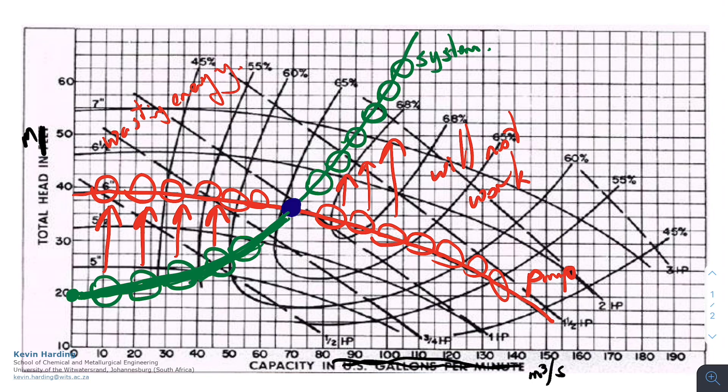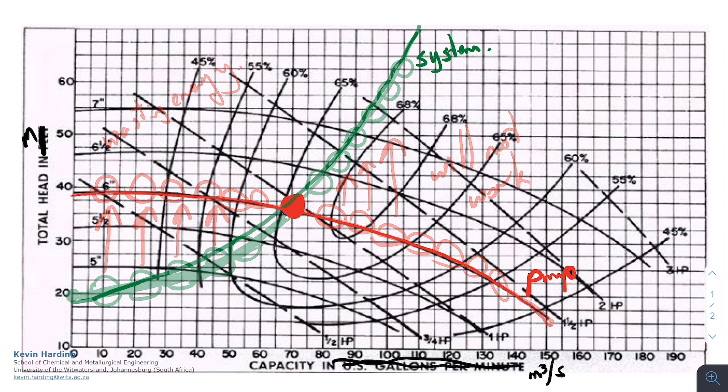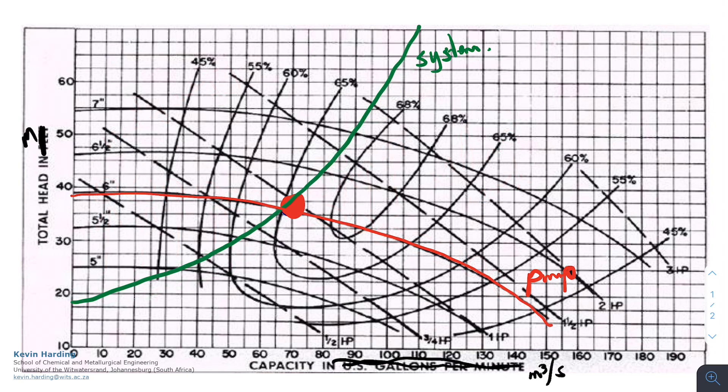So because of that, the point that we are going to choose as our operating point, the most efficient point on the graph, is going to be the intercept. So just neatening that up a bit, what we are now saying is that if we have a pump curve in the red and the green curve is our system curve, the point where the intercept is going to be our operating point. From that operating point, we can read off the actual Q value, and then along to the left, we can read off our actual head for this system with this six inch pump as in front of us.